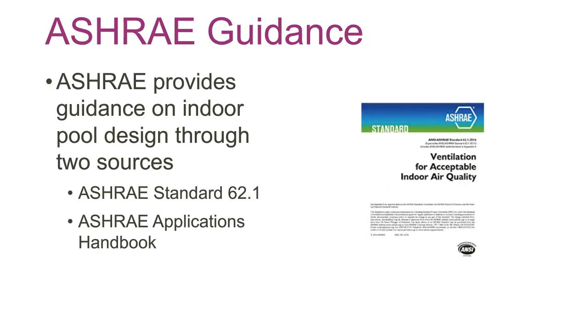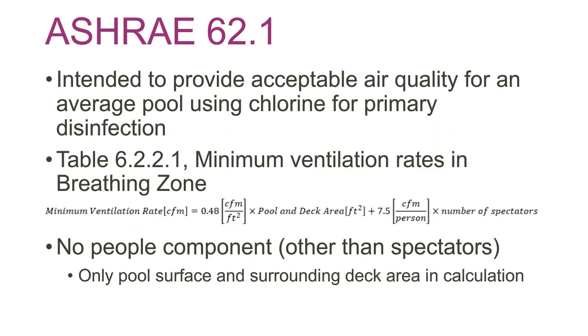ASHRAE has some good guidance on that. ASHRAE provides guidance on indoor pools through Standard 62.1 and also the ASHRAE Applications Handbook. There's a lot of good information in the handbook about designing all the things associated with pool spaces. ASHRAE 62.1 prescribes amounts of outside air. The handbook states that the amount in 62.1 is intended to provide acceptable air quality for an average pool using chlorine for primary disinfection. There's a table in there that specifies people and area rates for different places.